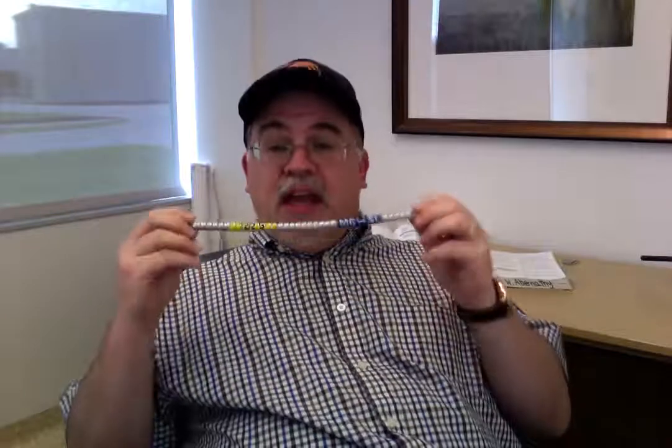In that case, you're going to look at 110.11. And 110.11 is going to say that a product has to be identified for its use. This is identified for a dry location. This is identified for a wet location. Thus, the more restrictive being wet clearly can be installed in a damp location. So the identification for this product can go both ways. This product cannot. Unless we identify this product for use in a damp location, it's a dry location only type product.